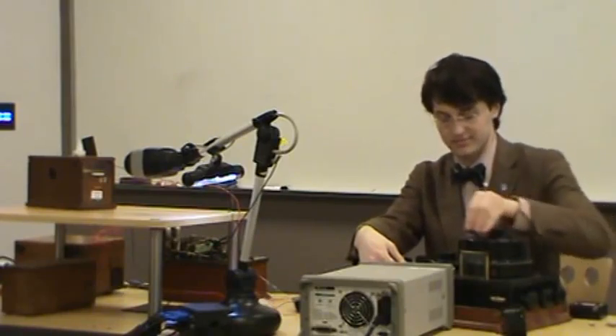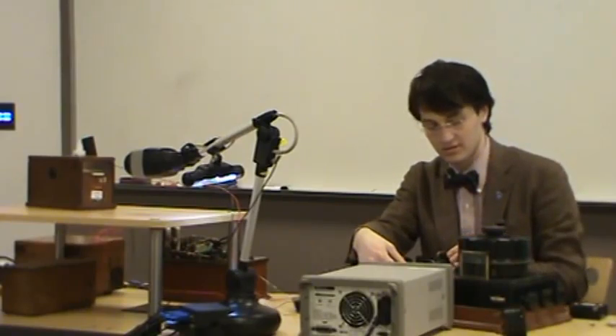So now we start working on our vernier knob here to reduce our deflection. You sort of have to watch where it averages because you lose good contact as you're spinning the thing. And that means that we need to change ranges. Some guy in his office whose job was to sit there and spin this thing. He's probably paid a lot of money to do it.